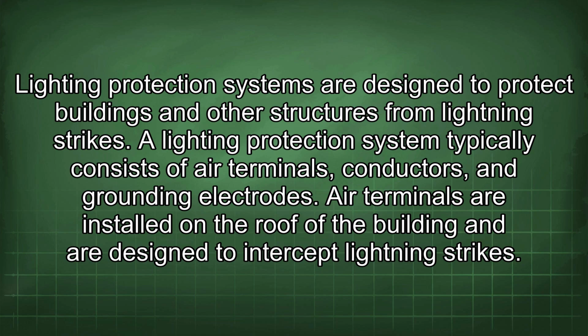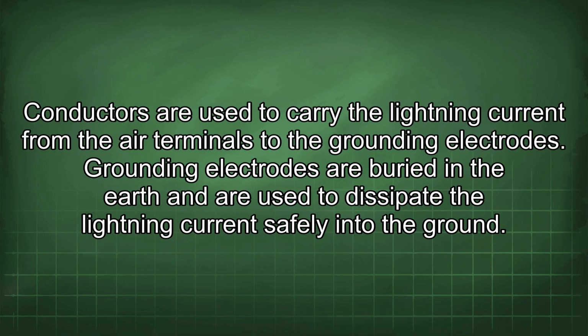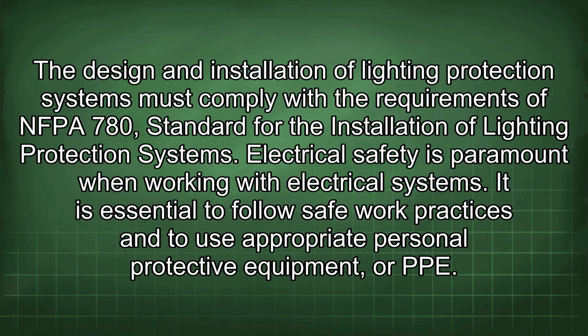A lightning protection system typically consists of air terminals, conductors, and grounding electrodes. Air terminals are installed on the roof of the building and are designed to intercept lightning strikes. Conductors are used to carry the lightning current from the air terminals to the grounding electrodes. Grounding electrodes are buried in the earth and are used to dissipate the lightning current safely into the ground.